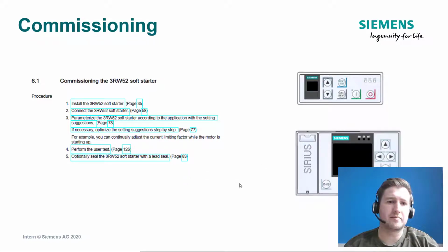So one of the really great features of programming with a 3RW52 is that you can actually integrate these optional HMIs. So this is the basic HMI and this is the advanced HMI. So the reason why you'd use one of these is it's really quick and easy to identify faults with. They are an extra cost, but in terms of the time consumption, identifying faults sometimes in wiring and how you've programmed the device can be quite time consuming because you have to decipher how the lights are flashing on the front of the unit, which isn't always easy, because there's different colours that the lights can go into, and they can either flash intermittently or stay on, and each individual light sequence can mean an individual fault, whereas if you're using one of these HMIs, you don't have to decipher that information.